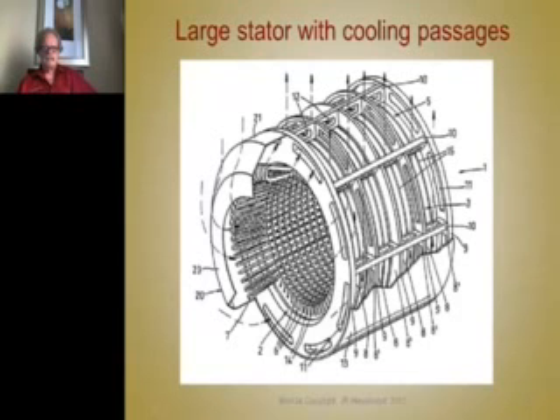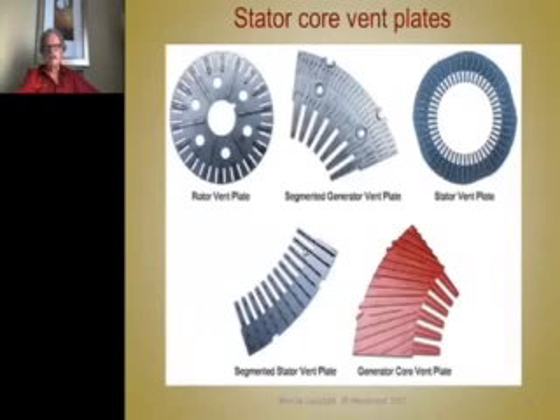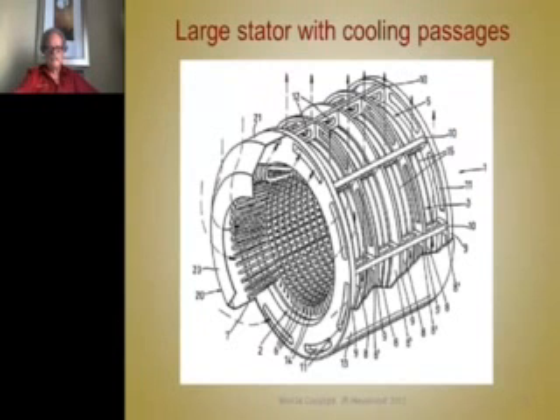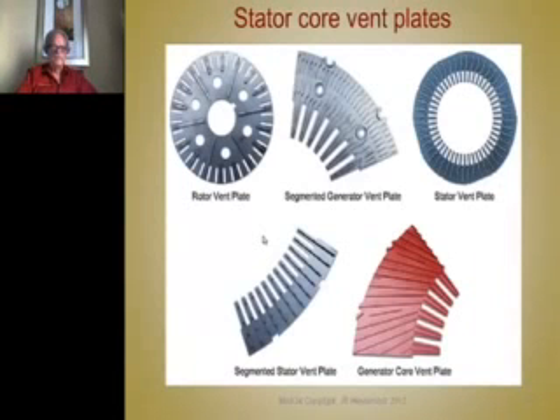And to aid in that, even the outside is made up of a welded structure with all sorts of vents in it. So there'll be some kind of a suction blower system that will suck air out of these chambers through all these passages, which will cause it to go from the inlets around the inside of the rotor through its vent passages, across the air gap and out these passages, because the rotor needs the same kind of cooling. It has conductors going down the slots as well. And these are those core vent plates that go between these laminated sections. There's ones for the rotor, this one's for the rotor, and these other ones are for the stator.